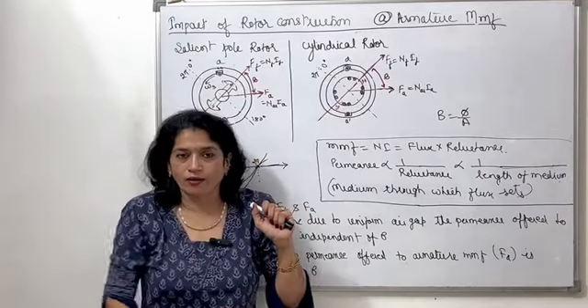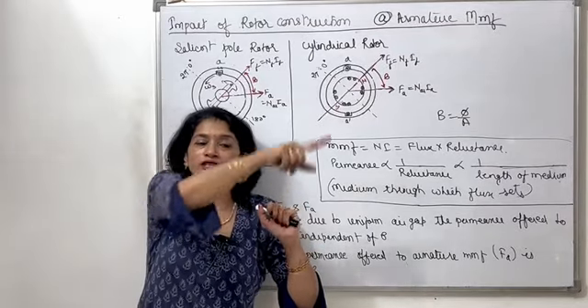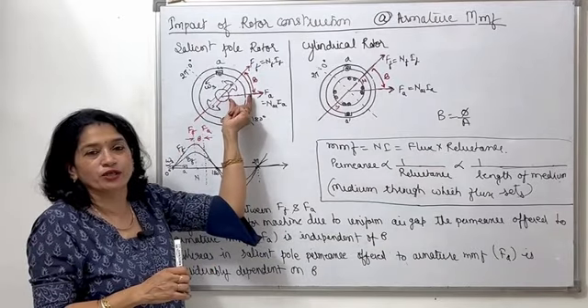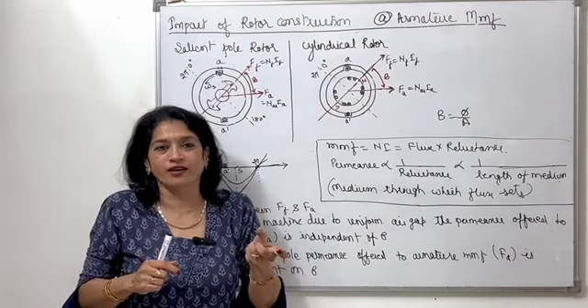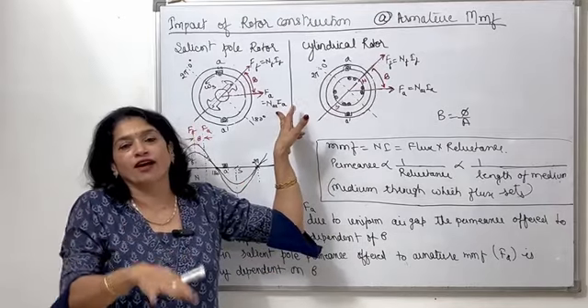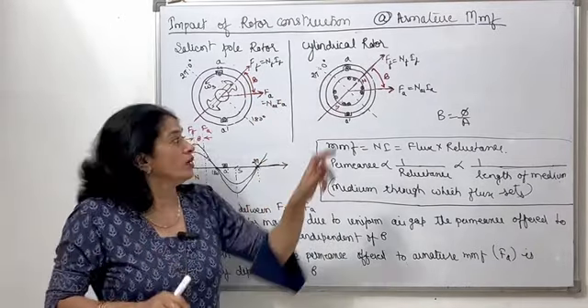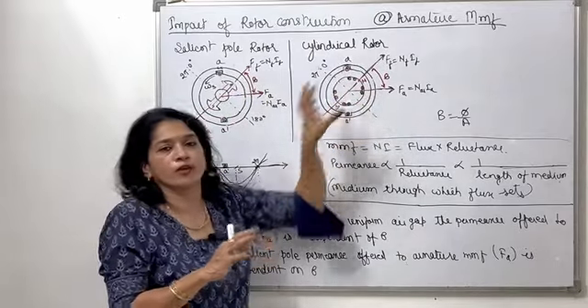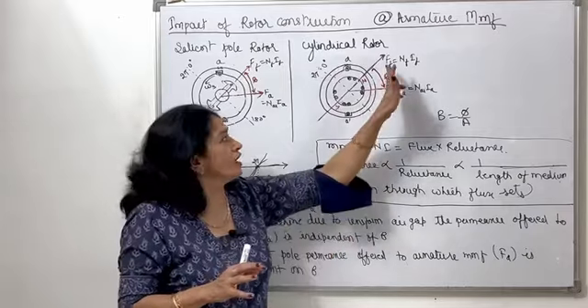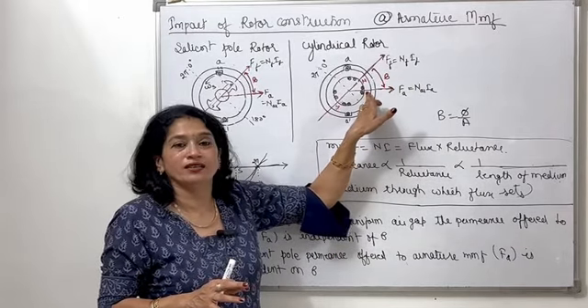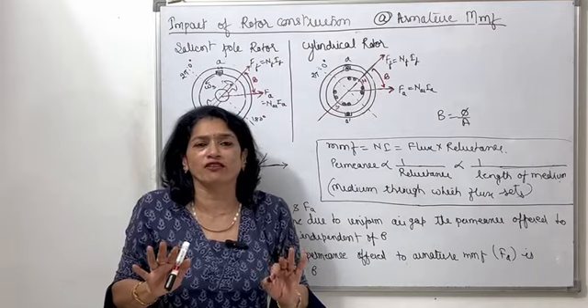How much FA is set depends entirely on the reluctance of the path. The flux loops of the armature MMF complete their path through the air gap. In the salient pole case, the armature flux finds a large air gap in its path at the interpolar region — this large air gap length means the MMF set or flux set is less. The quantity of armature MMF varies depending on the location of the rotor relative to the armature MMF direction.